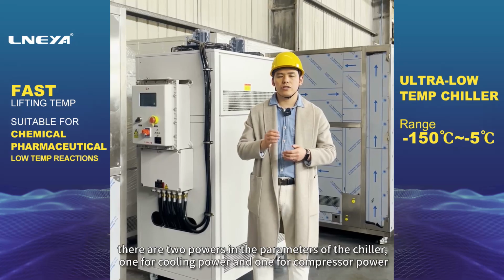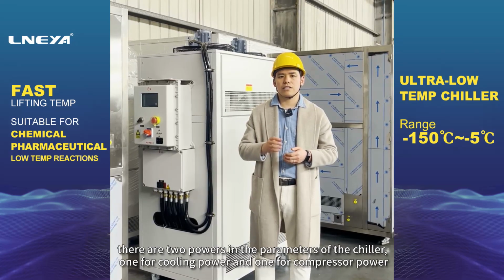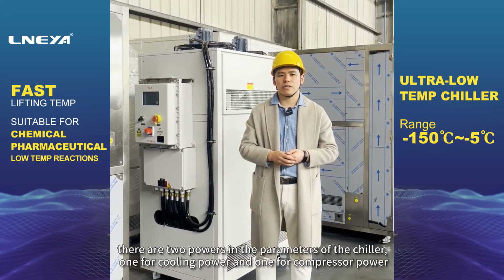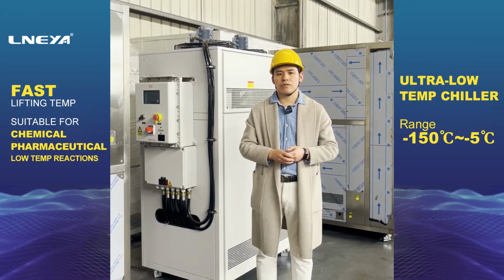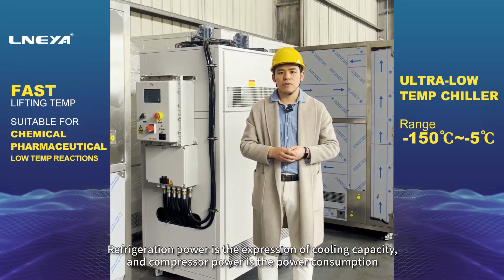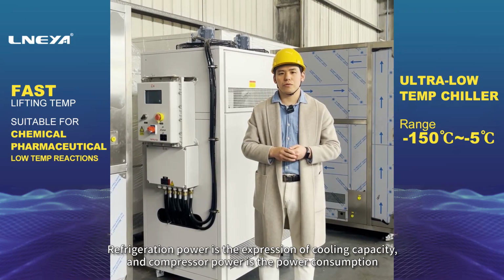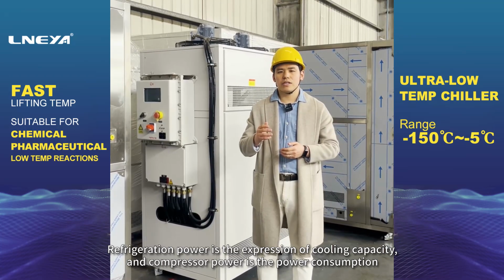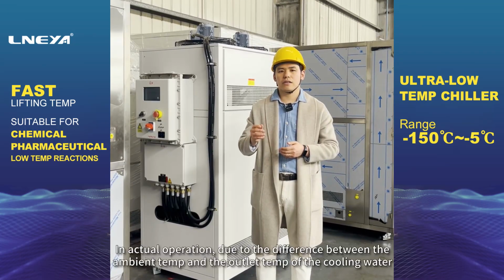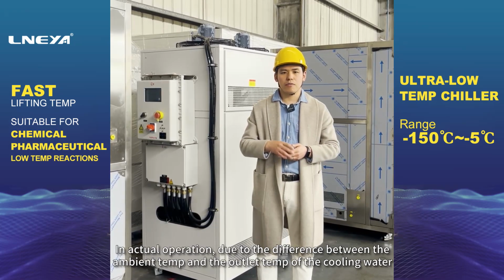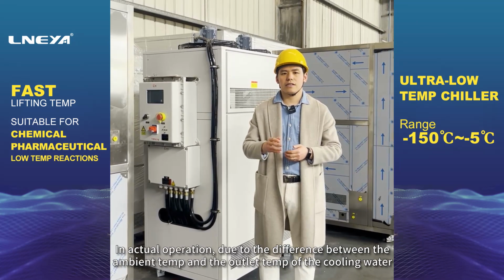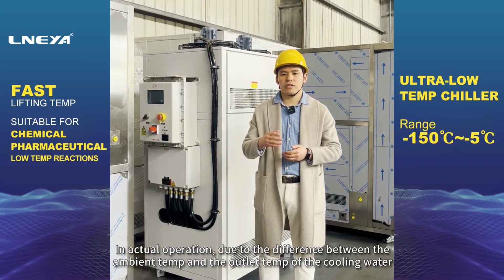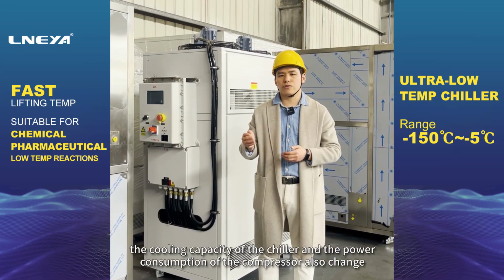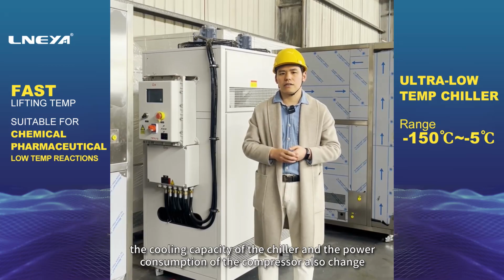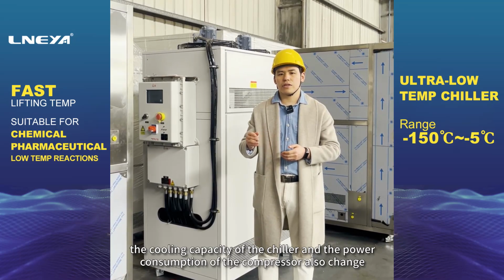There are two powers in the parameters of the chiller, one for cooling power and one for compressor power. Refrigeration power is the expression of cooling capacity, and compressor power is the power consumption. In actual operation, due to the difference between the ambient temperature and the outlet temperature of the cooling water, the cooling capacity of the chiller and the power consumption of the compressor also change.